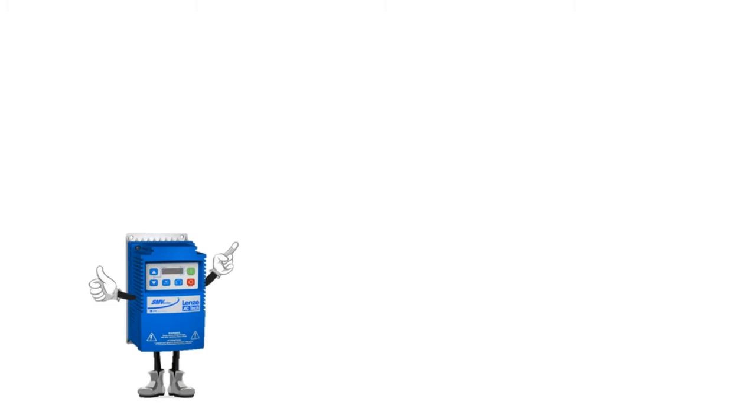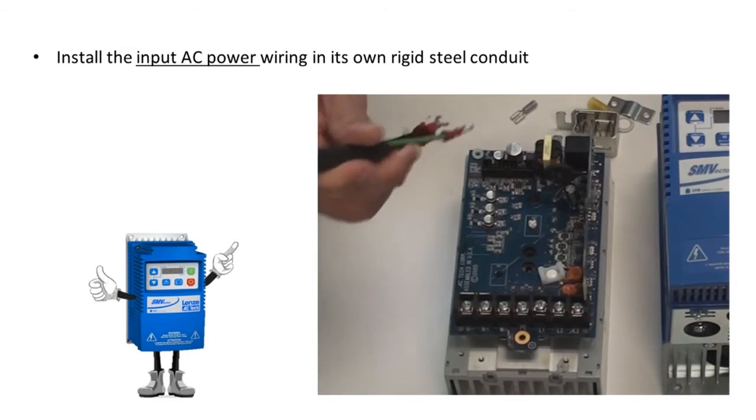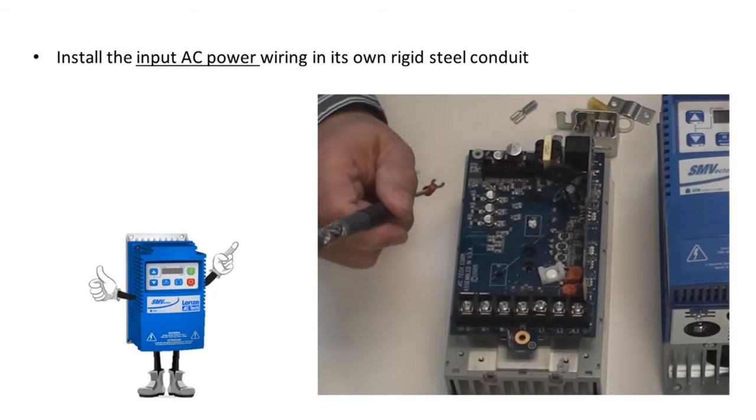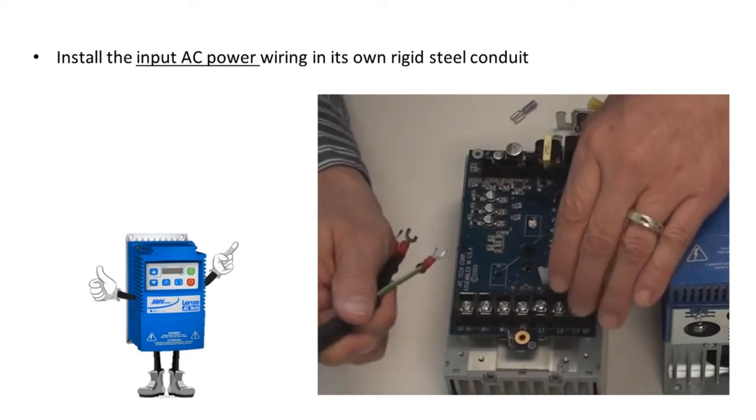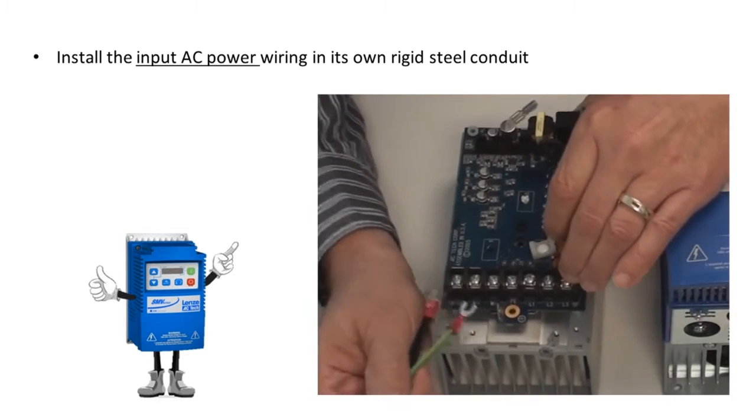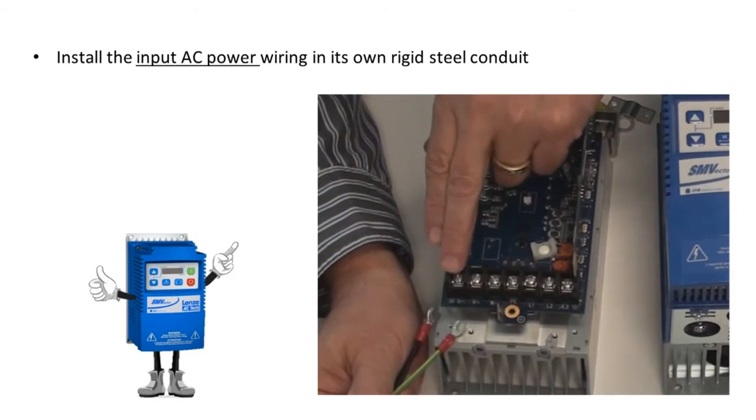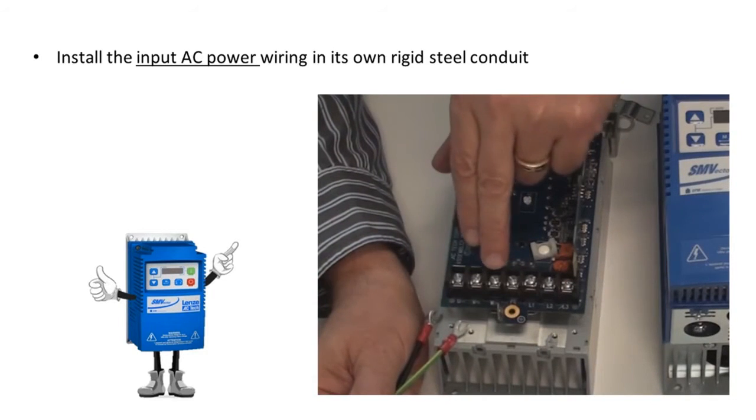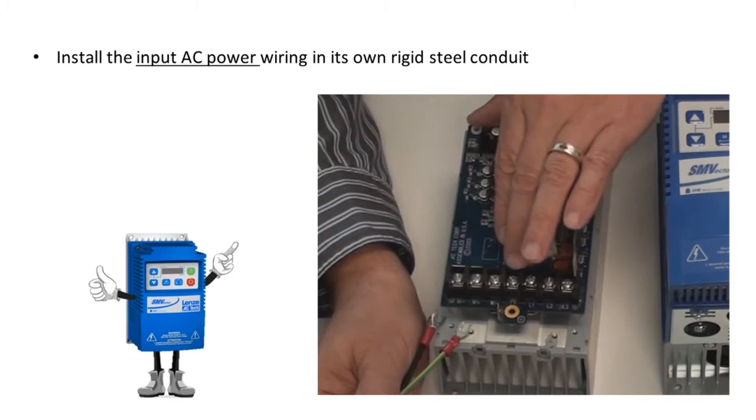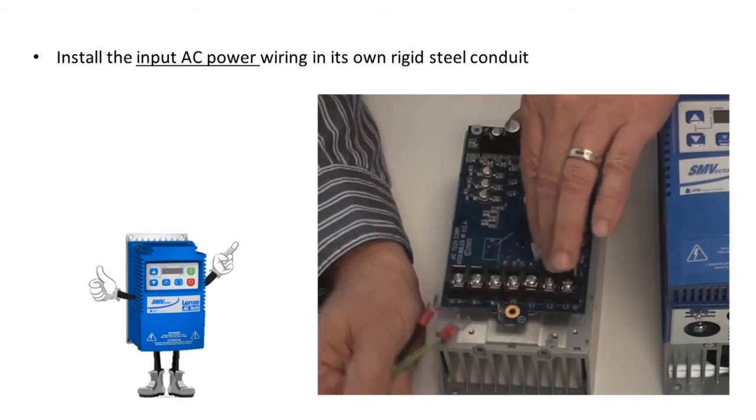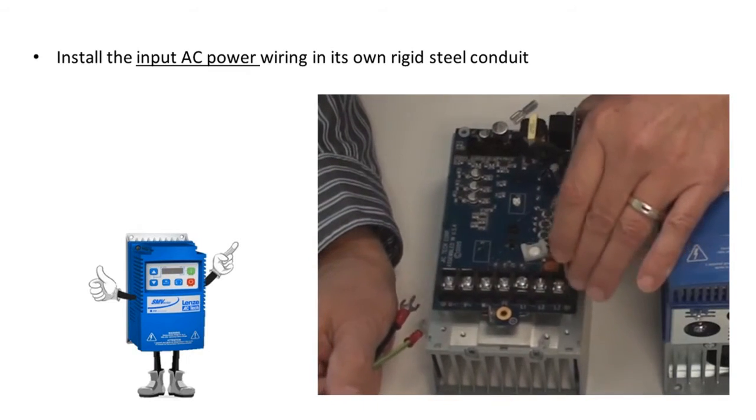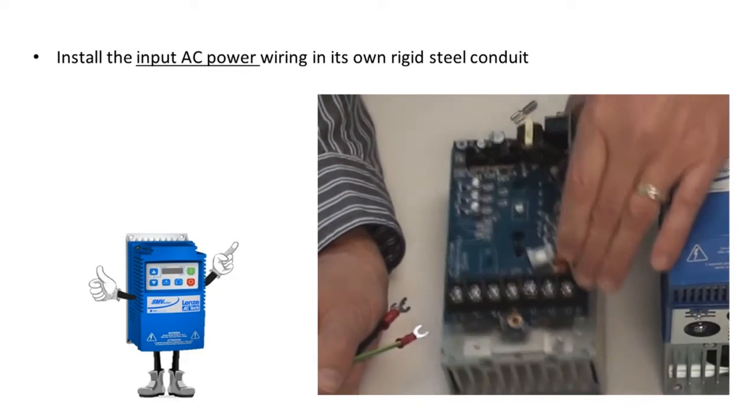One, install the input AC power wiring in its own rigid steel conduit. I have here a cable to illustrate that with the SM Vector drive. After you remove the bottom cover, you can see that we have our output wiring going out to the motor labeled U, V, and W, as well as the two ground screws. And then our input power connections are labeled L1, L2, and in this case L3, three-phase drive.